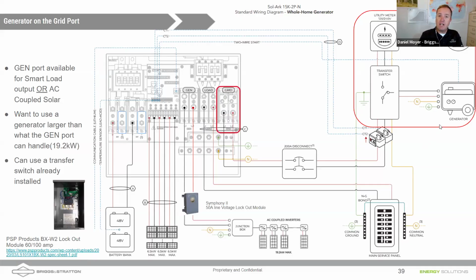In this example, when we start that generator, the generator coming into the grid port, as far as the solar array is concerned, that's grid, and it's going to revert back to a grid following situation. The danger here is that the AC coupled microinverters are going to recognize and latch onto the sine wave being produced by the generator and want to try and backfeed the generator. So we need to make sure that if the generator is running and the AC coupled solar is producing, we have a lockout module or a relay or something to be able to shut that AC coupled solar off.